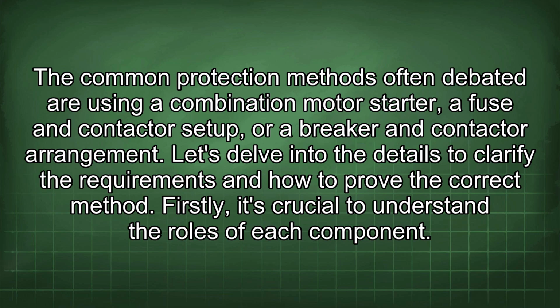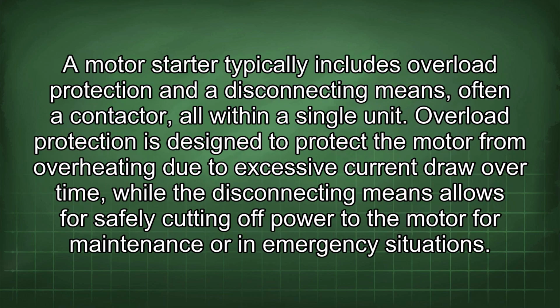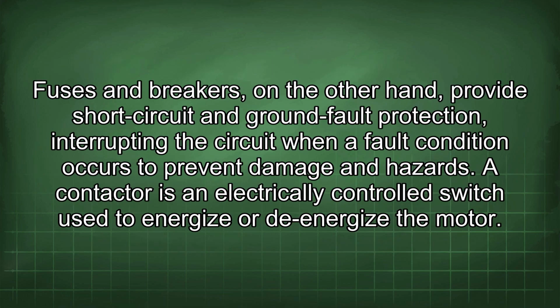Firstly, it's crucial to understand the roles of each component. A motor starter typically includes overload protection and a disconnecting means, often a contactor, all within a single unit. Overload protection is designed to protect the motor from overheating due to excessive current draw over time, while the disconnecting means allows for safely cutting off power to the motor for maintenance or in emergency situations. Fuses and breakers, on the other hand, provide short circuit and ground fault protection, interrupting the circuit when a fault condition occurs to prevent damage and hazards. A contactor is an electrically controlled switch used to energize or de-energize the motor.